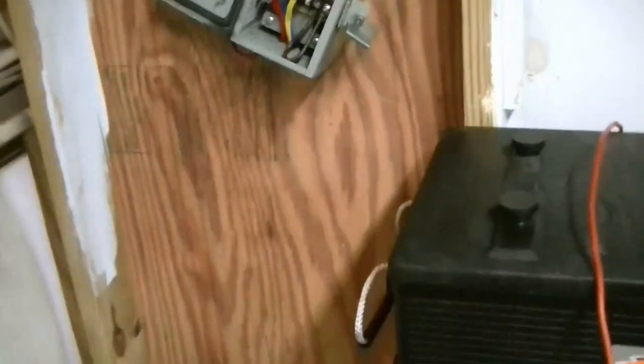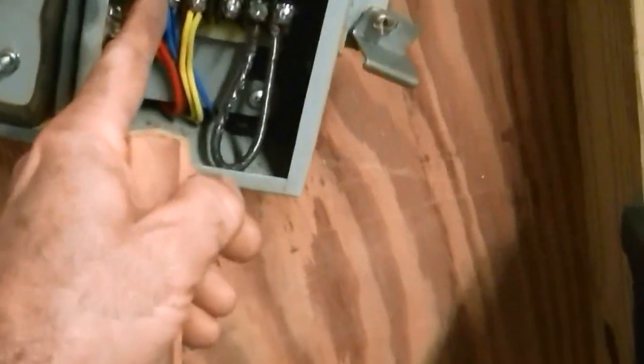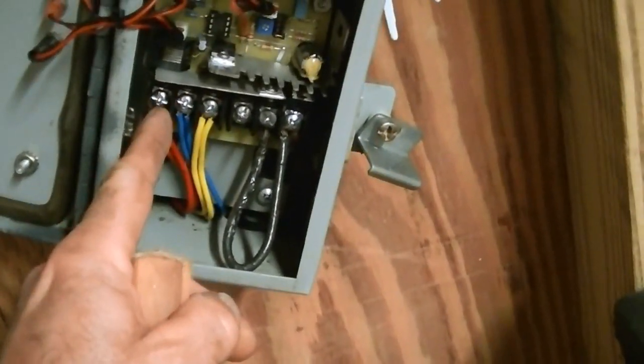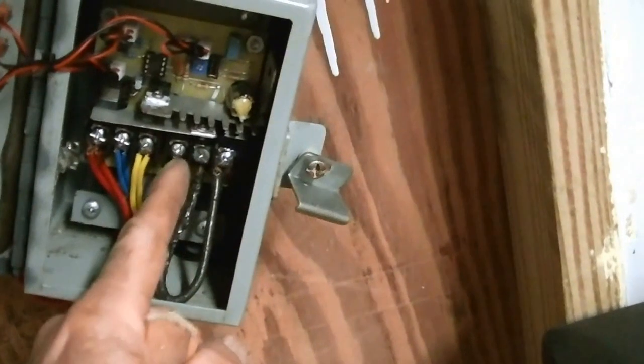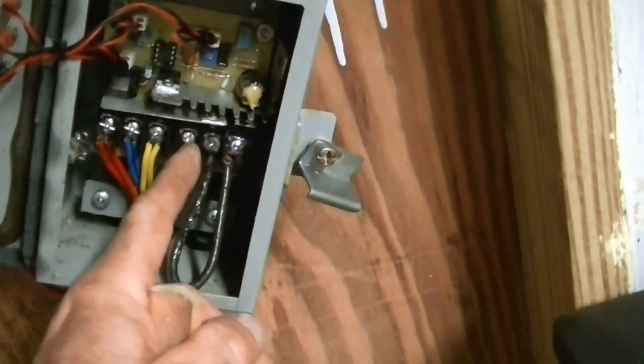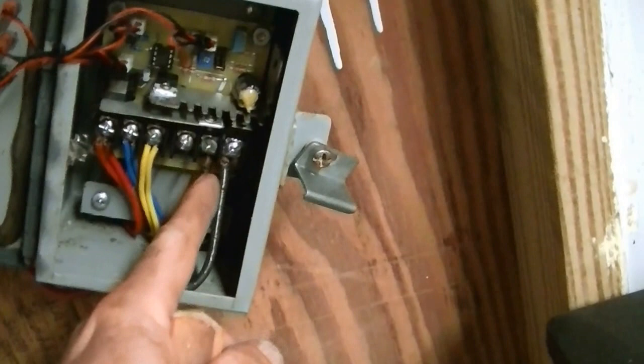This is the positive wire coming in from my solar array. It's only about 300 watts. It will hook into the far left terminal here, and the negative will go straight to the battery. Then another negative will run over to this terminal, and then a positive comes out of here over to the positive side. You have to add this little jumper wire when you're doing this system.